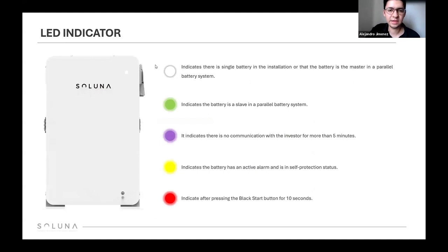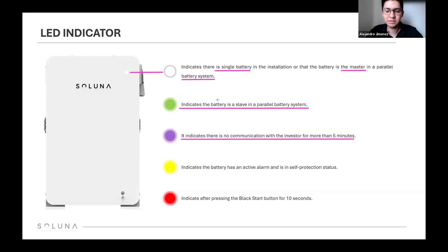Okay, we have the LED indicator. We have 5 statuses. If the LED is white, it means we have installed a single battery. Or if you have a parallel system, the master battery will be white. The slave batteries in a parallel system will change the LED to green. If the color changes to purple, it means the battery lost communication with the inverter; after 5 minutes without communication with the inverter, the LED will change to purple.